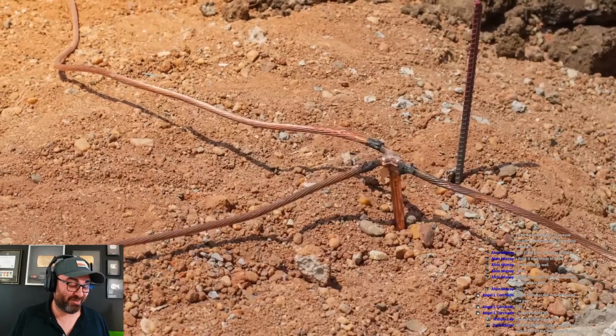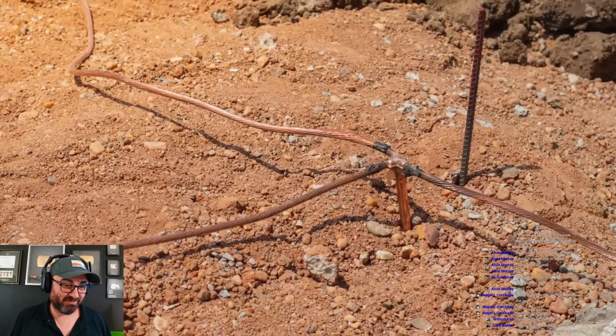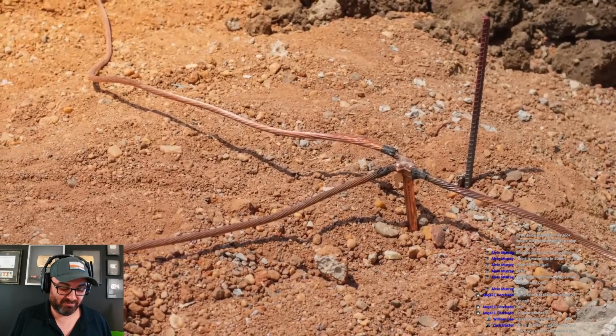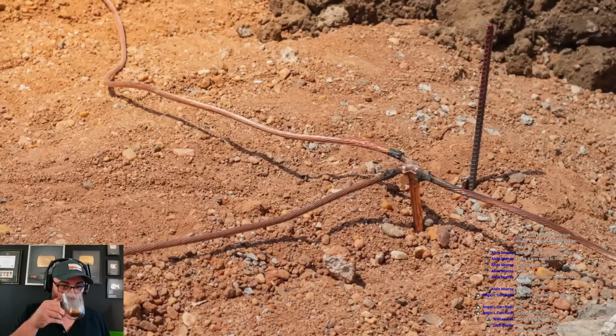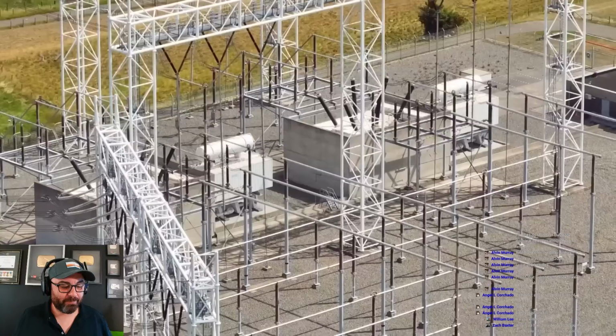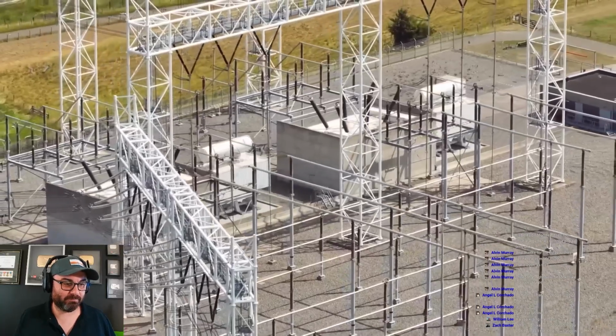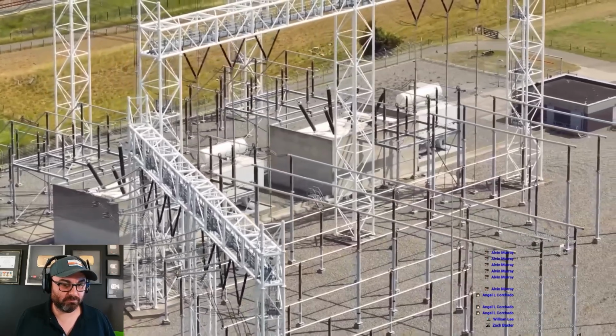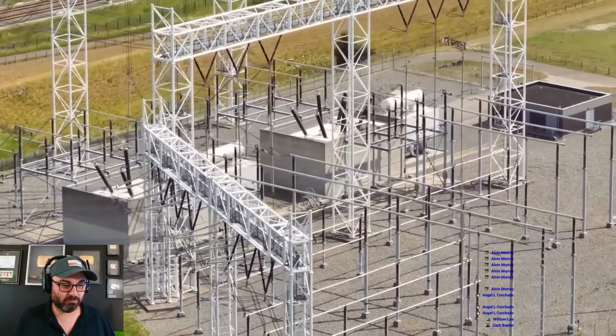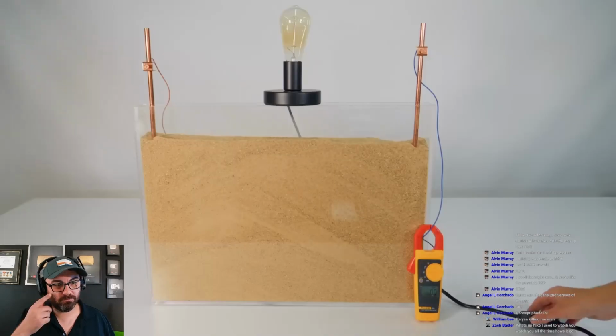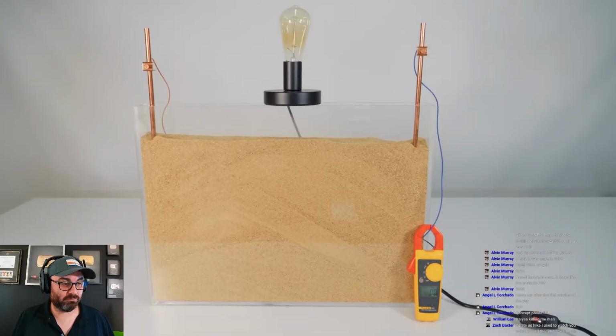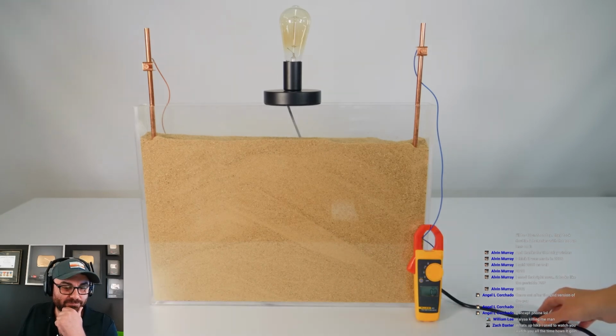For example, substations are equipped not just with a single grounding electrode, but a grid of buried conductors to minimize resistance in the earth connection. You might also notice that many substations use crushed rock as a ground surface. That's not just because linesmen don't like to mow the grass. It's because crushed rock, like the dry sand in my demo, doesn't conduct electricity well and minimizes the chance of standing water.